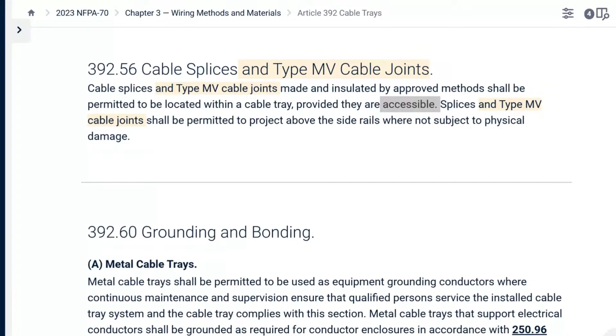Another good point is sometimes you have these cable tray systems that are rated, and they may have a rating to go through a 2-hour wall. So they put the cable tray into a segment that goes through the wall. Well, you obviously can't have splices in that segment because it's not going to be accessible. I mean, that should be common sense.